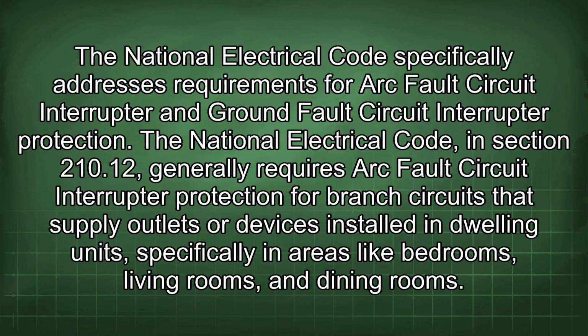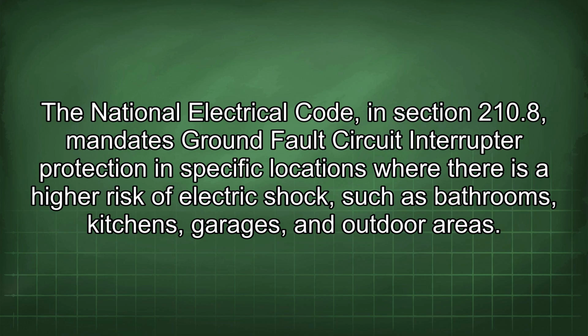The National Electrical Code specifically addresses requirements for arc fault circuit interrupter and ground fault circuit interrupter protection. The National Electrical Code, in Section 210.12, generally requires arc fault circuit interrupter protection for branch circuits that supply outlets or devices installed in dwelling units, specifically in areas like bedrooms, living rooms, and dining rooms. Section 210.8 mandates ground fault circuit interrupter protection in specific locations where there is a higher risk of electric shock, such as bathrooms, kitchens, garages, and outdoor areas.